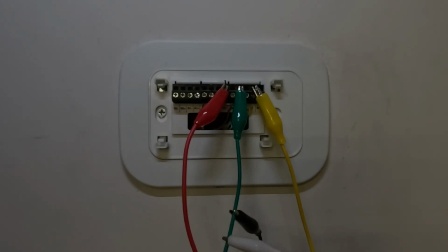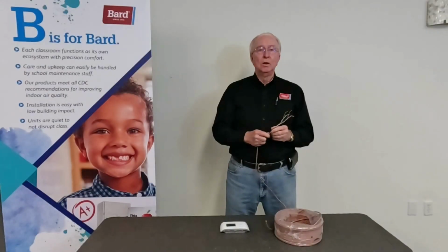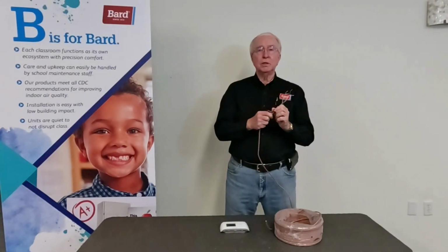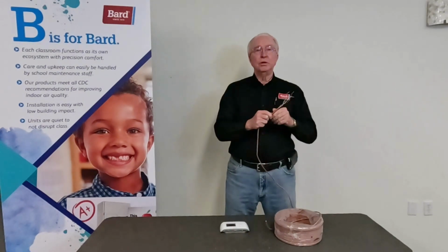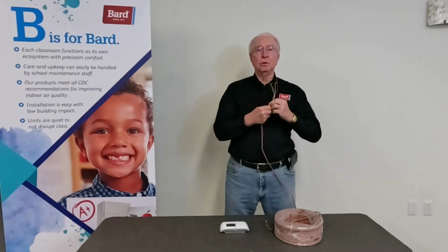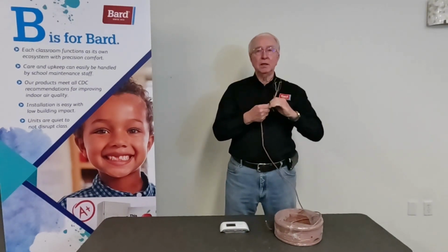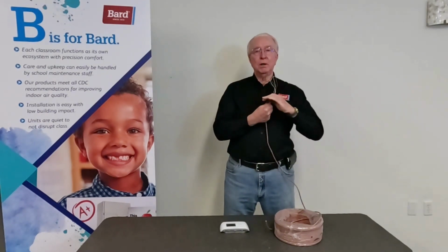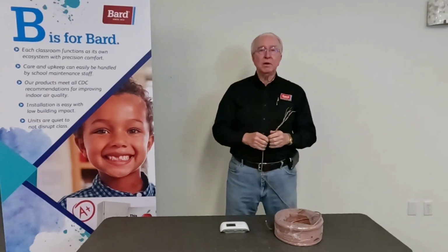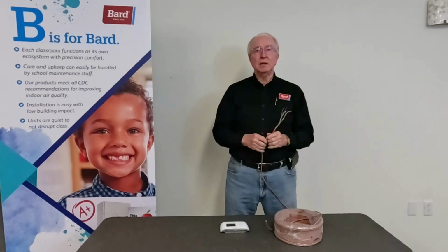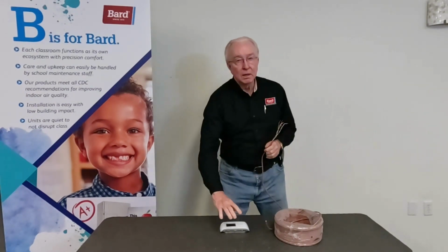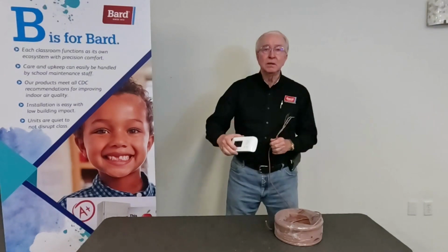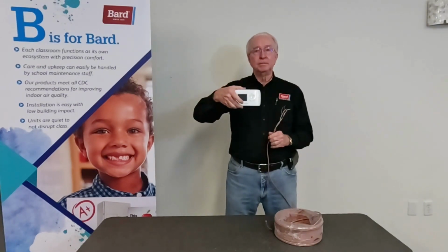If not, you may need to simply ohm out the stat wires to test for a shorted or open wire. When installing a unit or pulling new stat wire, always ensure you have a few extra conductors you don't need, just in case a conductor shorts or breaks later. This ensures you will have some spares to use. If you have an identical functioning unit and stat in the classroom or office next door, simply swap stats to see if that fixes the problem.